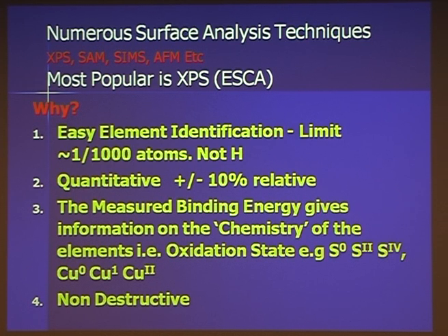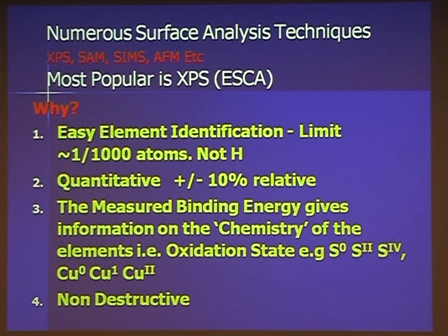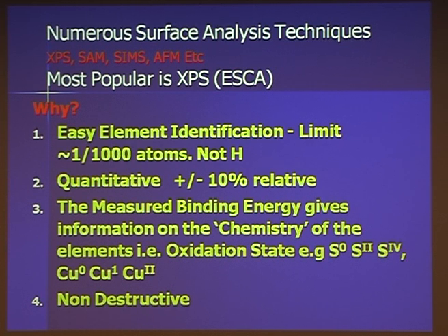Why is XPS so important? Very easy elemental identification, down to about one in a thousand — no questions asked. Reasonably quantitative. And something not too many other techniques are capable of in a short time: you measure the binding energy of these electrons, and it gives you the chemistry of the elements — what the oxidation state is. For example, whether it's sulfur, sulfur 2, sulfur 4, or copper 0, copper 1, copper 2. This requires a bit of processing with XPS software. And in general it's non-destructive, though some fluorinated polymers are a little damaged during XPS analysis.